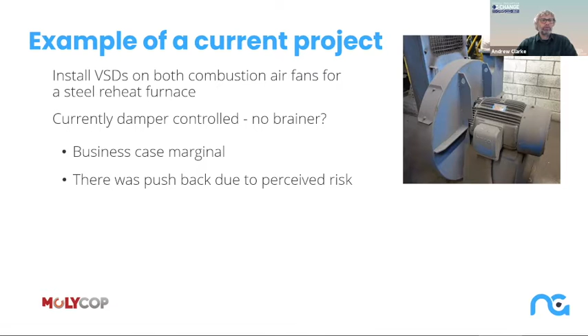There's also pushback due to a perceived risk in making that change, since it means an altered burner airflow control mechanism. Currently they have 3 zones, and 2 of those zones are on one fan, so there are 2 separate dampers controlling the flow to each zone. We're proposing to install a combination of variable speed drive flow control and a damper on one zone that will work in parallel.